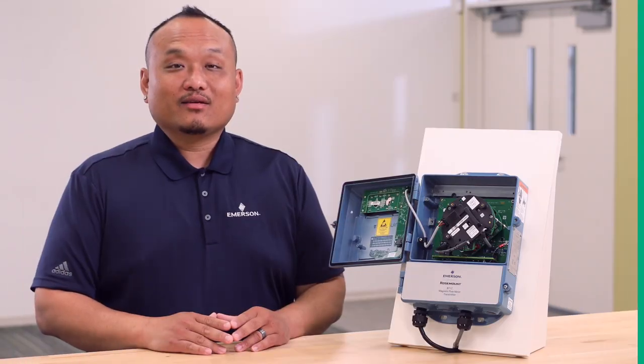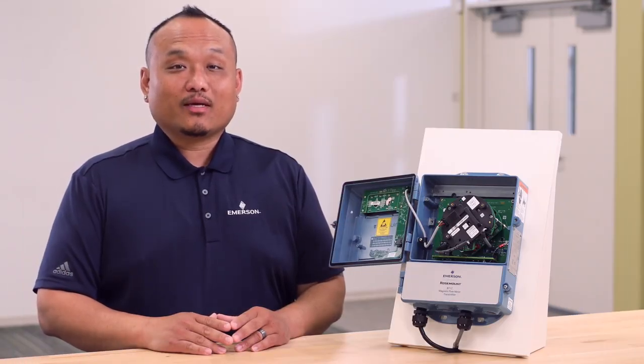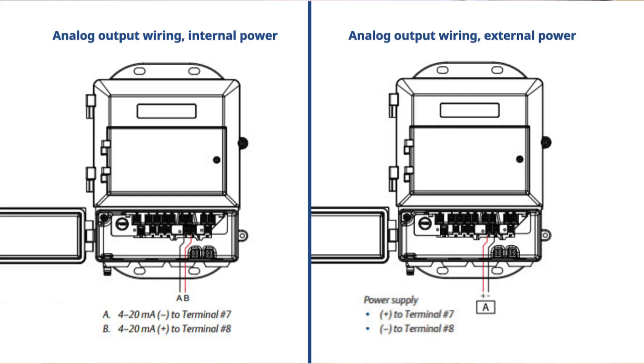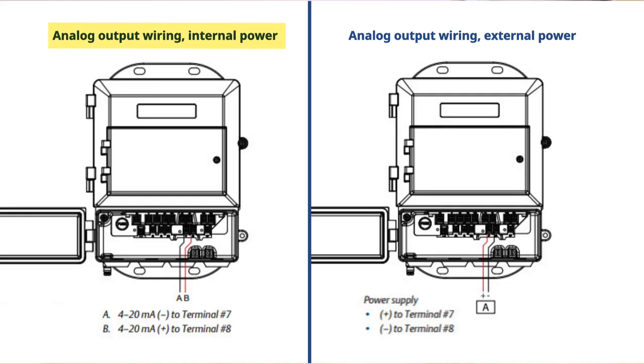Second, verify the analog 4 to 20 milliamp loop wiring. If the transmitter is supplying loop power, the positive wire must land on terminal 8 while the negative wire lands on terminal 7. If there is an external power supply powering the analog output, the negative wire must land on terminal 8 while the positive wire lands on terminal 7.